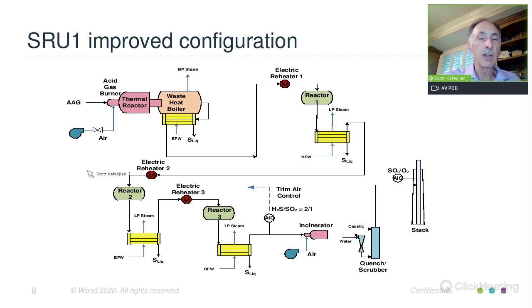So the improved configuration here, the first thing to notice is there are now electric reheaters for each reactor inlet. Reactor 3 is back in service. The air control will be improved and a new analyzer installed. The incinerator now is a forced draft incinerator with a blower and operates with the outlet going directly to the quench and scrubber, and then from the scrubber outlet directly into the upper section of the stack.